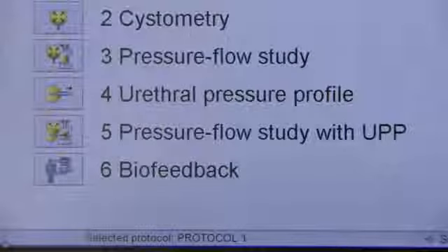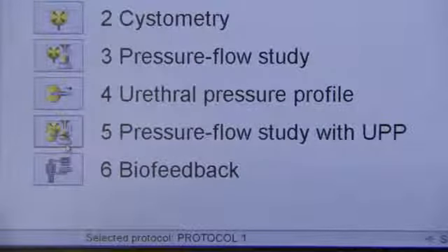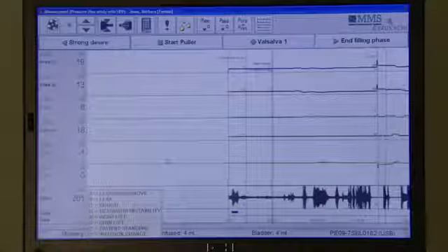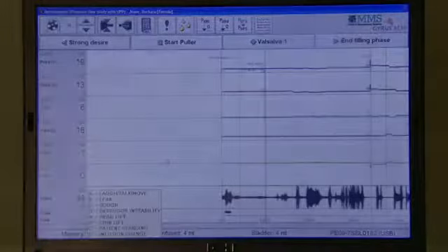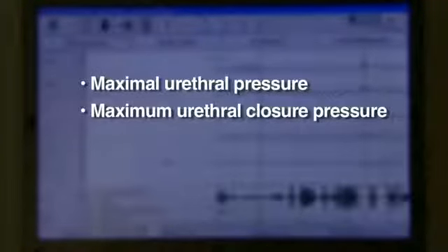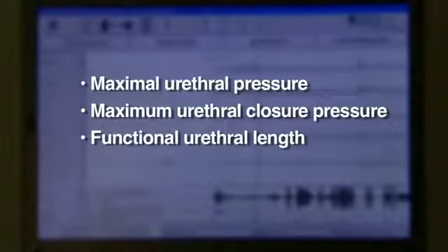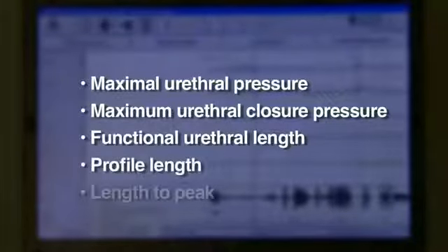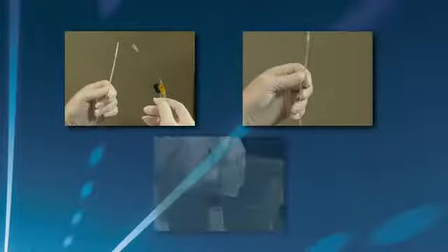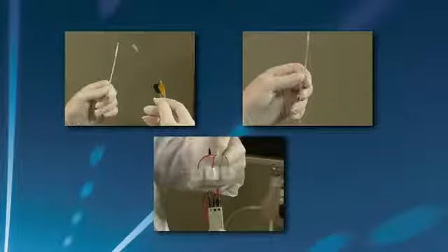The puller works in conjunction with an optional pressure flow study with UPP program. This study allows the user to complete up to 10 comprehensive urethral pressure profiles anytime during the test. UPP results include maximum urethral pressure, maximum urethral closure pressure, functional urethral length, profile length, and length to peak. This UPP study utilizes a dual sensor catheter, abdominal catheter, and EMG leads.